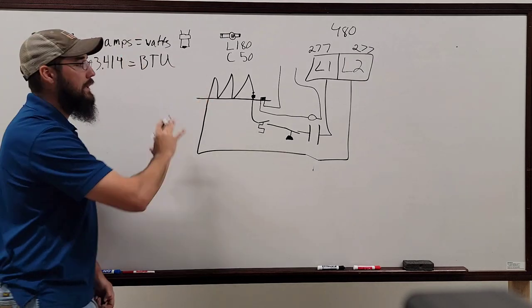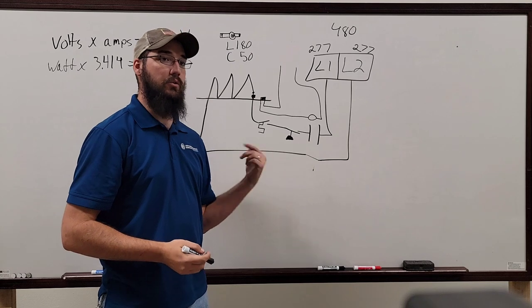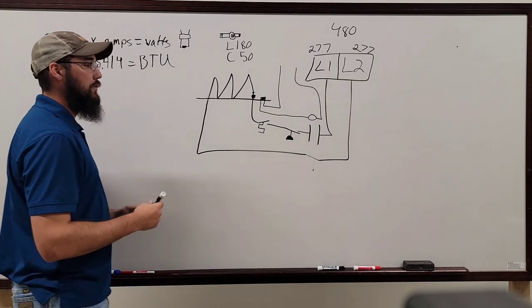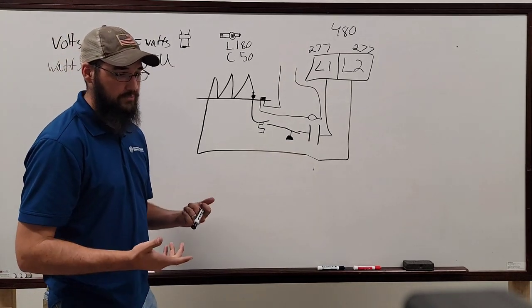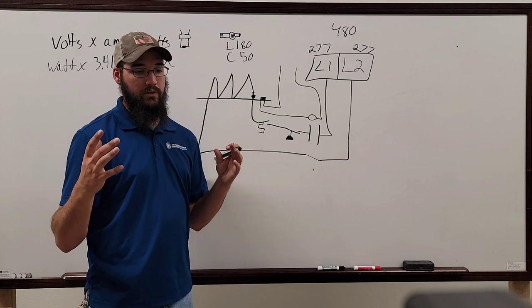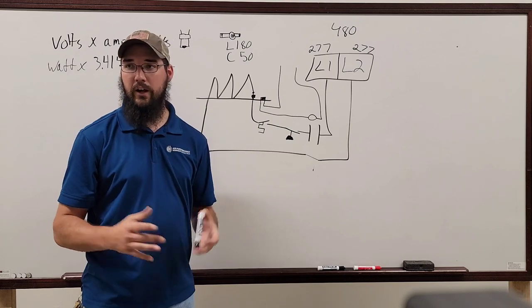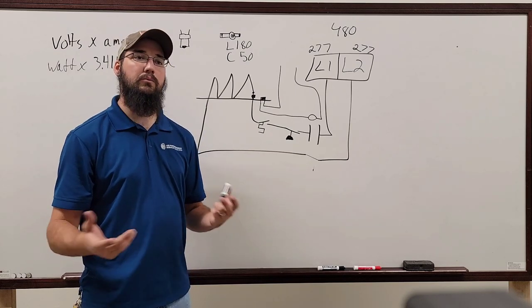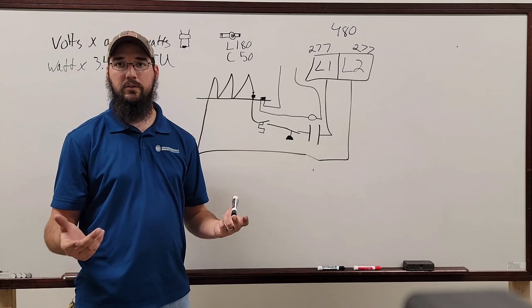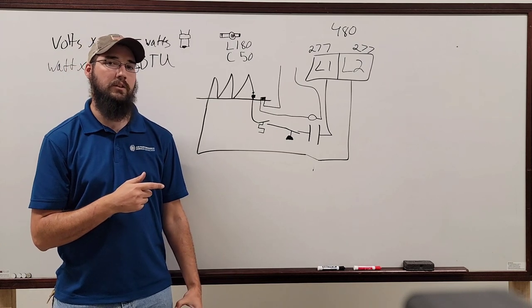If it ever helped, if you needed to know what kW your heater was, you can also reverse engineer that. If you know on the sticker, say you've got a two-stage heater, so you've got two heats, and it's a 10 kW heater at 460 volts, well, it's pretty easy math at that point. You know that each of those heat strips is going to be 5 kW, because what's on that tag is an accumulation of what's installed. Does that make sense?